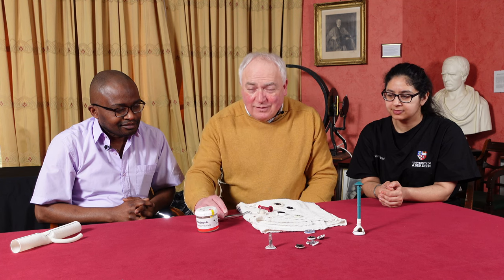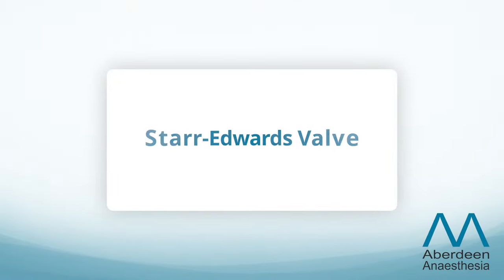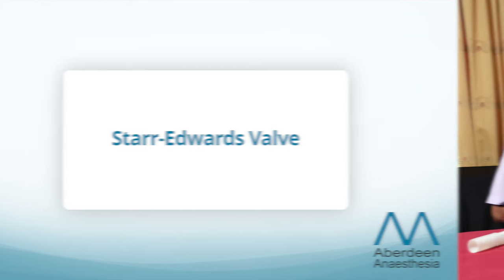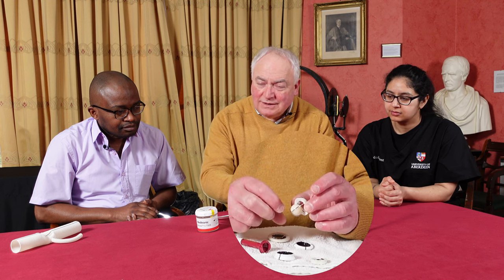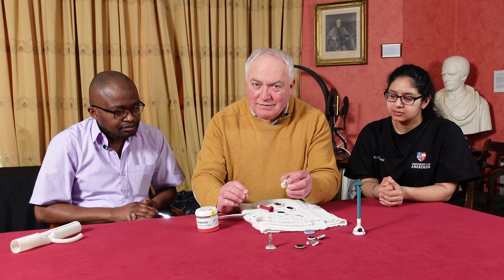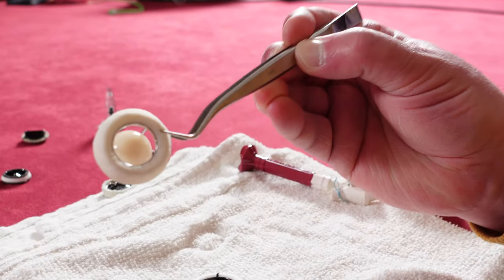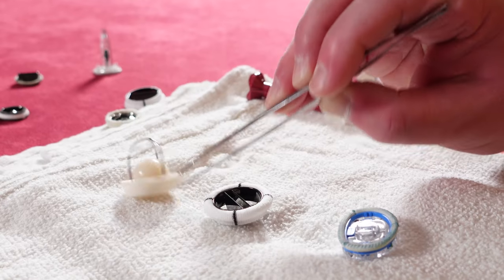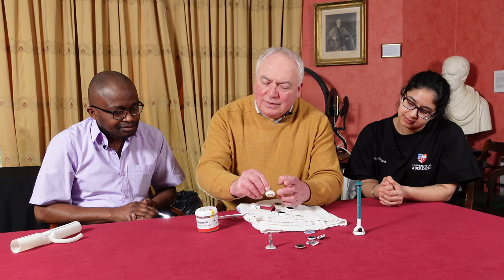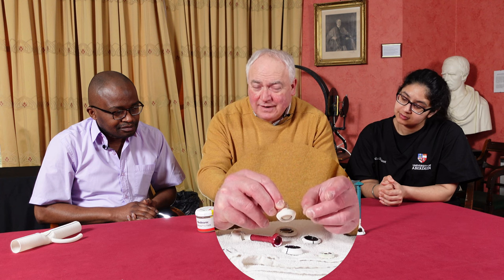I've brought along some heart valves to show you how they have evolved over the decades. The first heart valve to come into widespread use was this ball and cage valve, called the Starr-Edwards valve. It went through a variety of modifications, including one with a metal ball which ran along special tracks — famous for being the loudest artificial heart valve ever created. The final version has a rubber ball. Occasionally when we sew these valves into the aortic valve annulus there's a leak called a paravalvular leak or paravalvular aortic regurgitation.